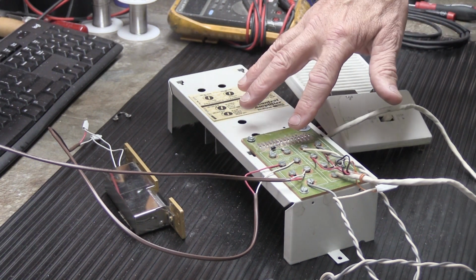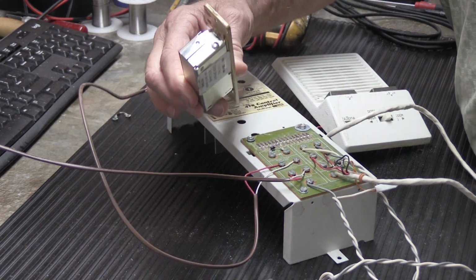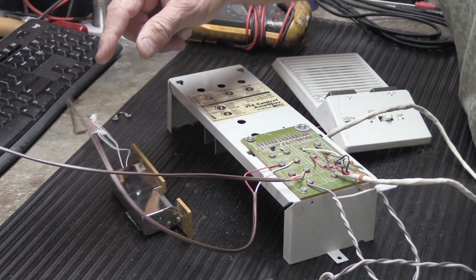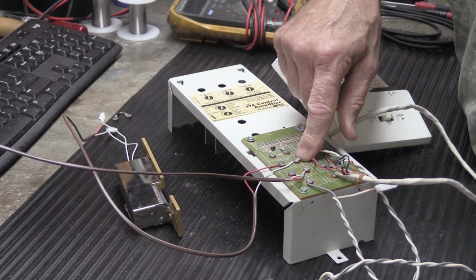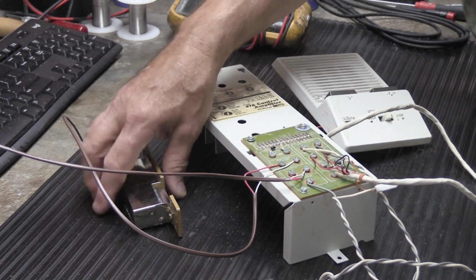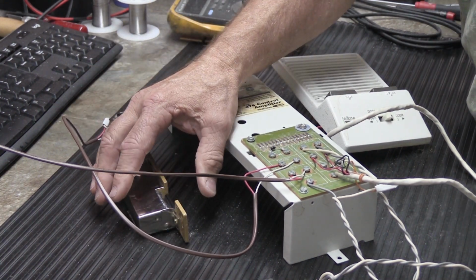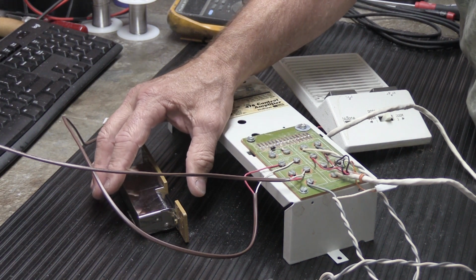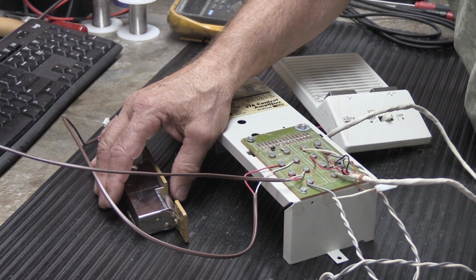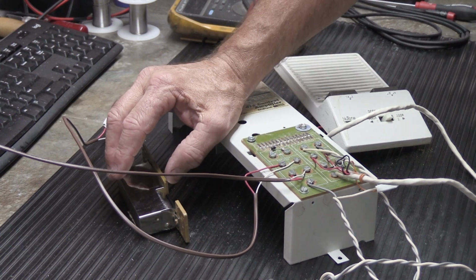More likely, it could be a problem with the 478 control amplifier, or it could be a problem with the door release itself, or it could be a problem with the wire that connects the door release to the 478. One of the questions I always ask people when they call about door release problems is, is it on, for instance, a wooden entry door that's part of the building, or is it an ironwork gate that's in front of the building or on the sidewalk? Because those can create different situations.